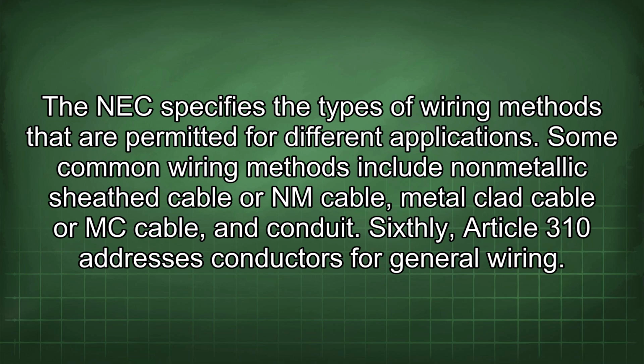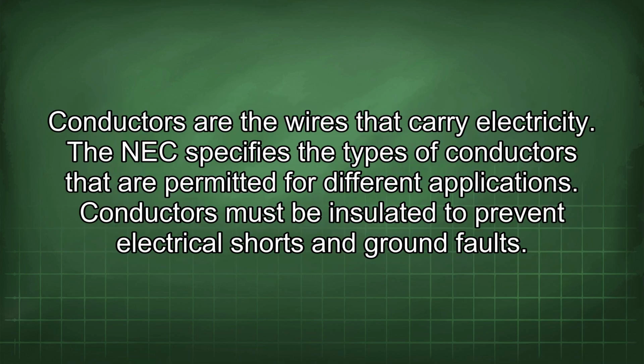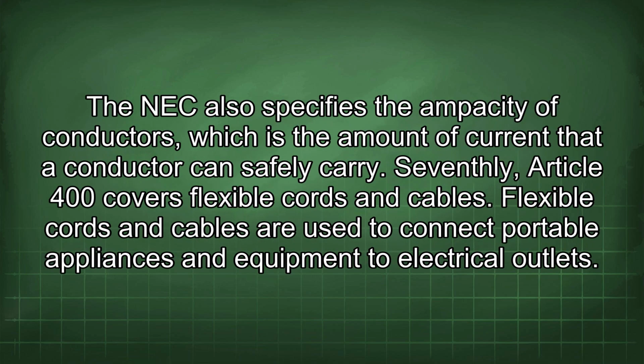Sixthly, Article 310 addresses conductors for general wiring. Conductors are the wires that carry electricity. The NEC specifies the types of conductors that are permitted for different applications. Conductors must be insulated to prevent electrical shorts and ground faults. The NEC also specifies the ampacity of conductors, which is the amount of current that a conductor can safely carry.